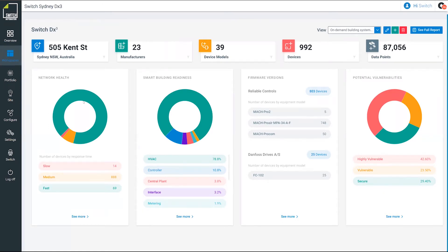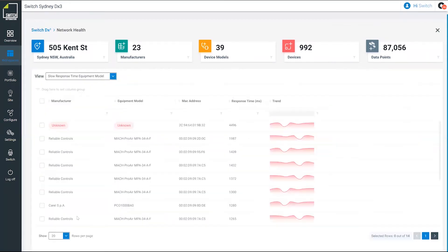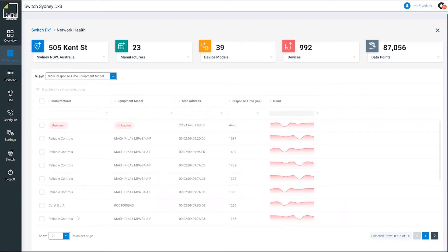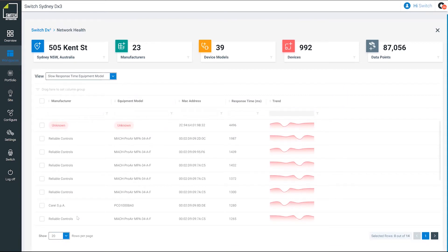On the left-hand side here, we've got a bit of a network health check because anyone that's done any building systems integrations before will know that any latency on the communications bus is problematic, especially for a visible layer like switch automation where we're charting, we're doing fault detection. Data quality is very important. If we're getting any latency on controllers, then that's going to compromise the sensor information that's coming up to the platform.